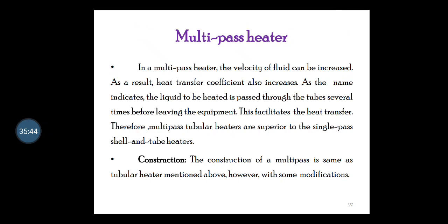Next will be the multi-pass heaters. In a multi-pass heater, the velocity of the fluid can be increased. As a result, the heat transfer coefficient also increases. As the name indicates, the liquid to be heated is passed through the tube several times before leaving the equipment. This facilitates the heat transfer. Therefore, the multi-pass tubular heaters are superior to the single-pass shell and tube heaters.